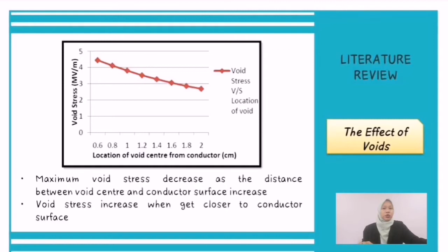It can be observed that maximum void stress decreases as the distance between the void center and the conductor surface increases. Void stress increases when it gets closer to the conductor surface, and as the void gets further away from the conductor surface, the maximum void stress will decrease. As a result, a void closer to the conductor surface is hazardous to the cable insulation breakdown.